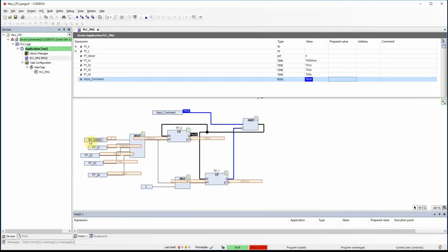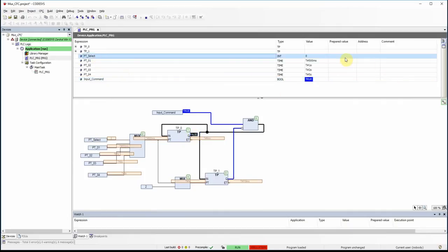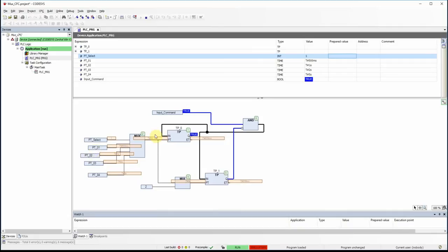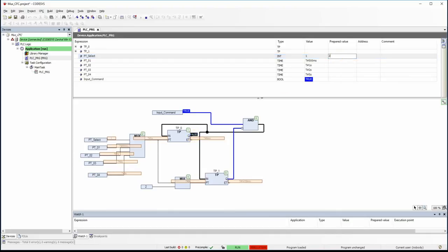Now if I change the pt_select value from 0 to 1 and press F7 and Alt+F7 to force it, the second value — 1 second — appears as the preset time of the first timer, and we have 2 seconds as the preset time of the second timer. Our pulse width is now 1 second on, 1 second off.